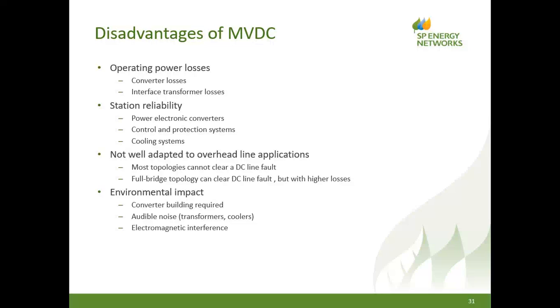There are topologies that can clear DC faults. A full bridge topology, a more complex topology, could clear a DC line fault, but the operating losses and the capital costs will be higher. So we're going to see how this pans out. If we have suffered a lot of DC line faults, we may decide that this has not been a good application. If the DC line faults are within an acceptable bound, maybe this is a good application of DC technology.